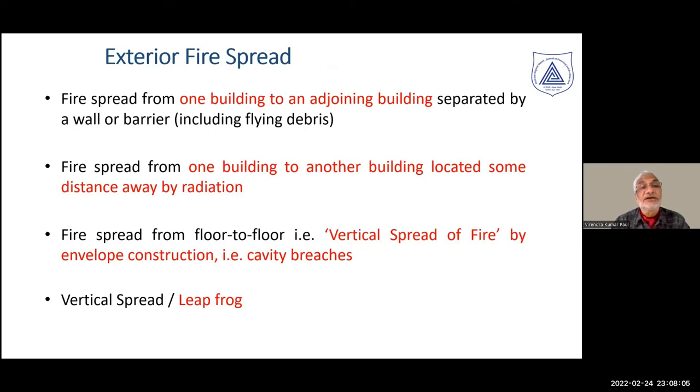External fire spread, as we saw, is largely related to spread from one building to an adjoining building, where a wall or barrier separates them, protecting against flying debris. Another mechanism is fire spread between buildings by radiation. A third option is fire spreading within the vertical cavity created between the building envelope and the structure — these cavity breaches across floors work like a chimney and spread fire vertically very fast.